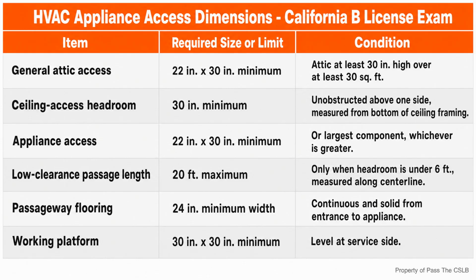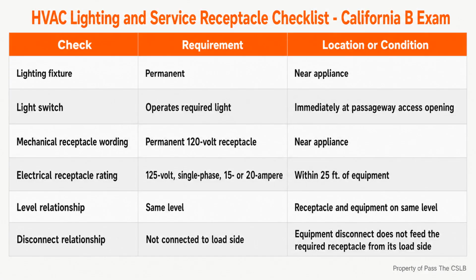If the outlet were fed from the load side, opening the disconnect would also de-energize that outlet. The checklist on screen separates the light and receptacle decisions. The light fixture is permanent and near the appliance. Its switch is immediately at the access opening. The servicing receptacle is within 25 feet on the same level, and not on the load side of the equipment disconnect. These are different checks, even when one coordinated installation satisfies more than one requirement.